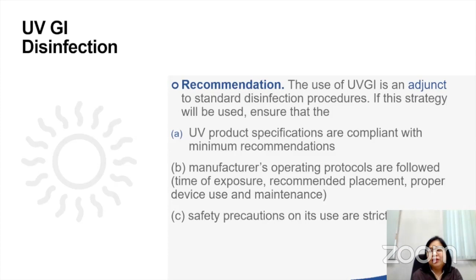So how about instrument cleaning, disinfection, and sterilization? We're done with the room, but we now have to think about how we do the instrument cleaning and how we clean the rest of the environment. For non-critical equipment which need cleaning and low-level disinfection, regular detergent and household bleach are often not enough to remove blood and organic debris. And this is why sometimes you see your clamps having some more blood that seems to have already gone through the autoclave, but there's still organic debris there. And that's not good because biofilm does contain significant bioburden and can pose a risk for infection.